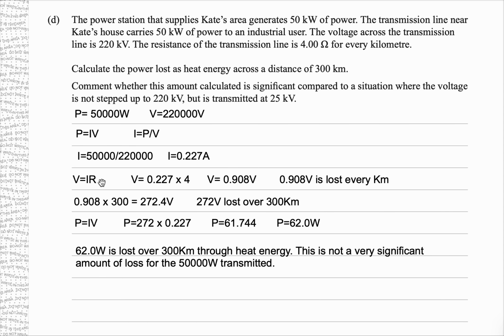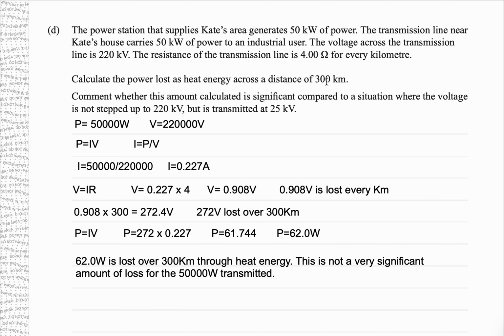Then calculate the voltage loss every kilometer, which is just the value we got, 0.227, times the resistance of 4 ohms. That gets you 0.908 volts loss every kilometer. Then times that by 300, because there's 300 kilometers, which gets you 272 volts loss over the 300 kilometers.